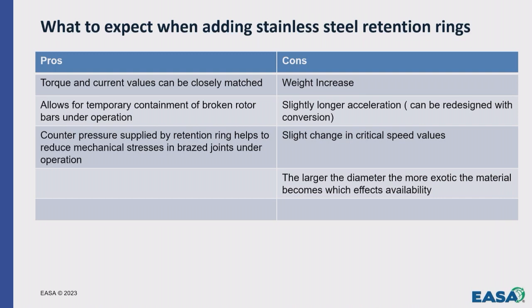So you change it to a copper alloy, and you are able to successfully duplicate the rotor cage resistance, which means that your torque and amp performance values are going to remain consistent. They're not going to change, which is good for your customer and good for the application.